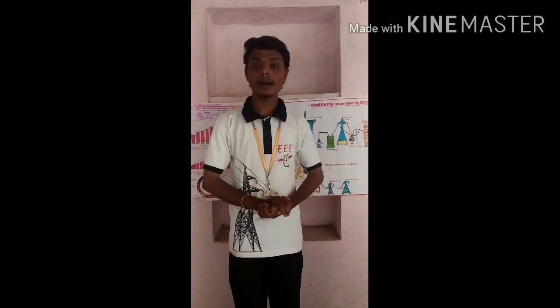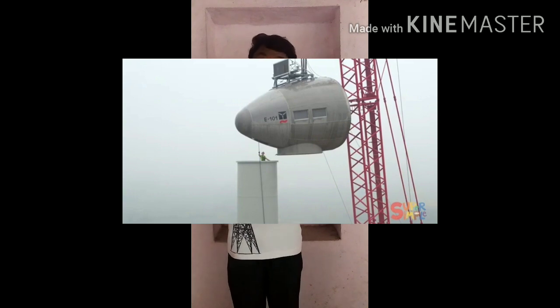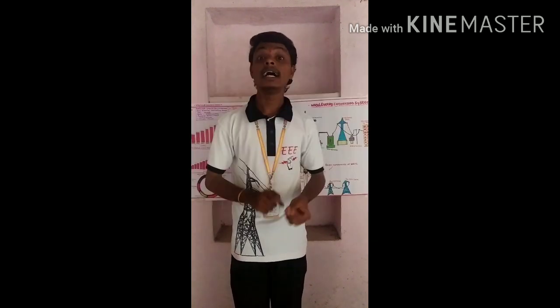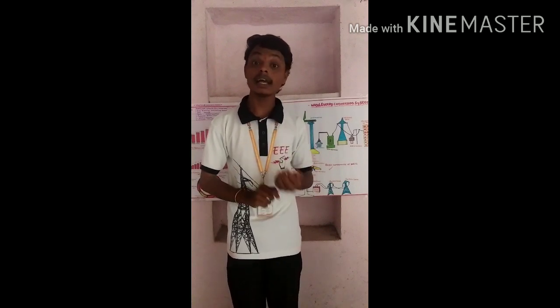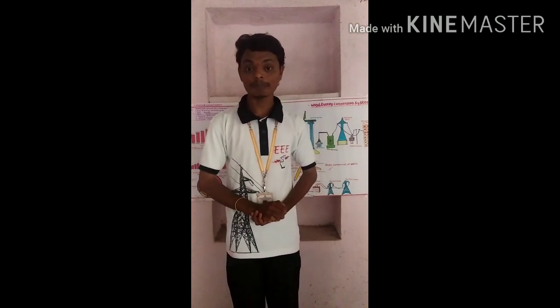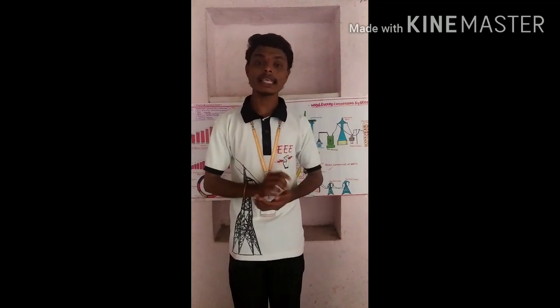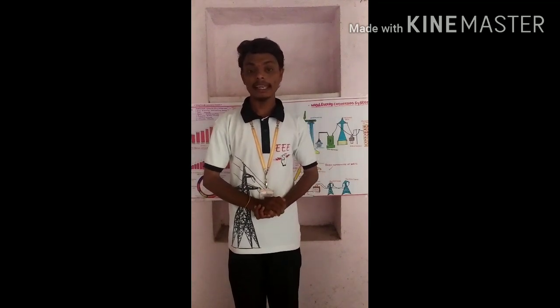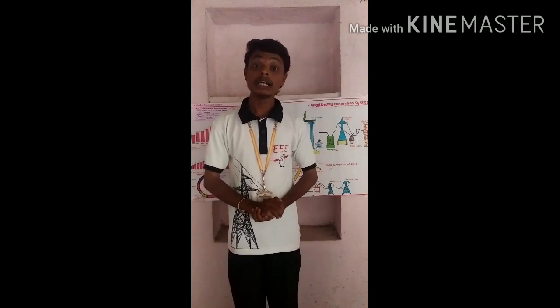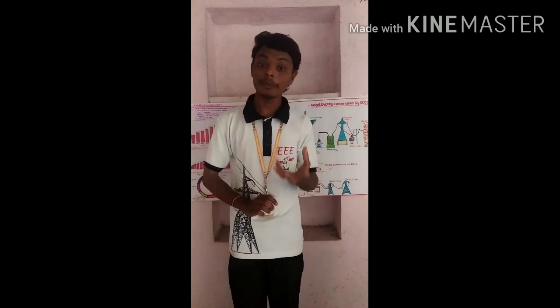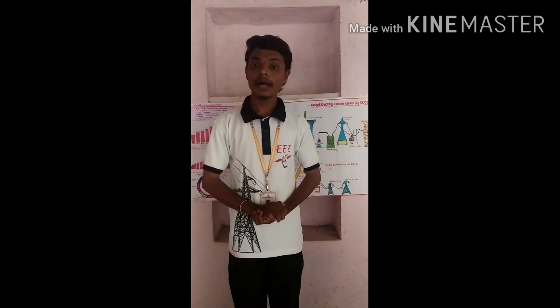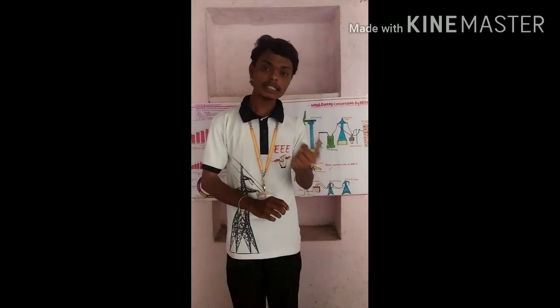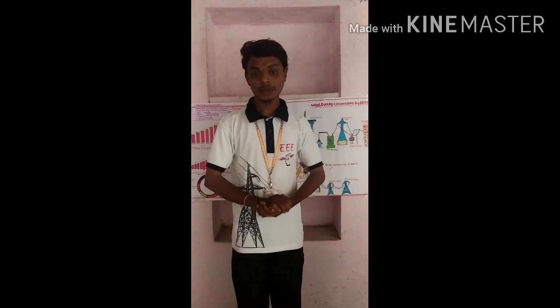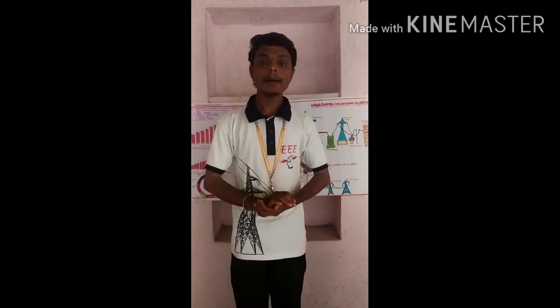Next component is the hub. It acts as a base for the rotor blades and extenders. It also houses the control system for the pitch drive. It rotates freely and is attached to the nacelle by means of a shaft and bearing. This is the function of the hub. Next component is the pitch drive. It sets the optimum angle for the desired wind speed and rotational speed. The pitch of the blades is controlled by using the pitch drive. For each blade, a separate drive system is used. This is the function of the pitch drive.